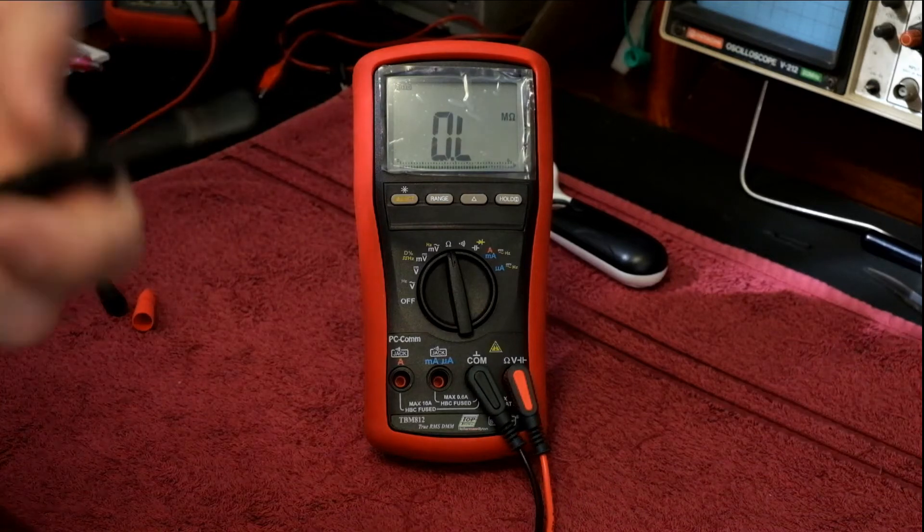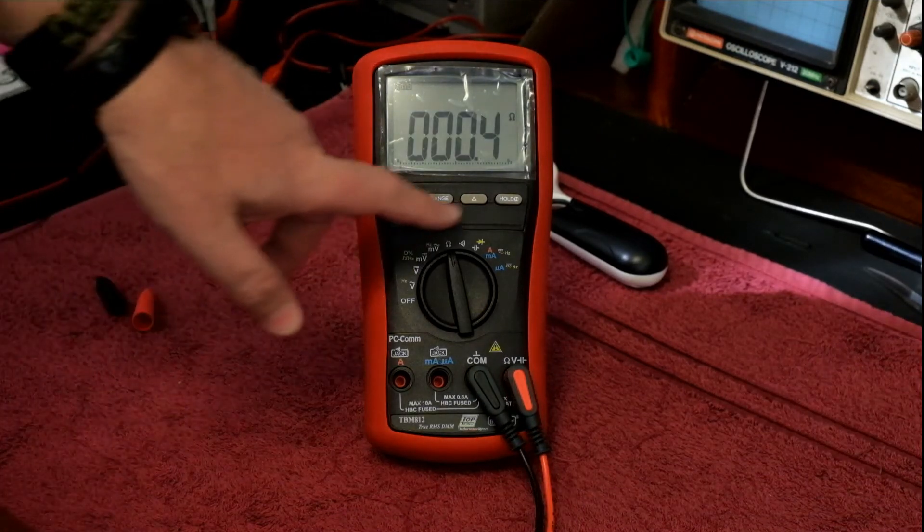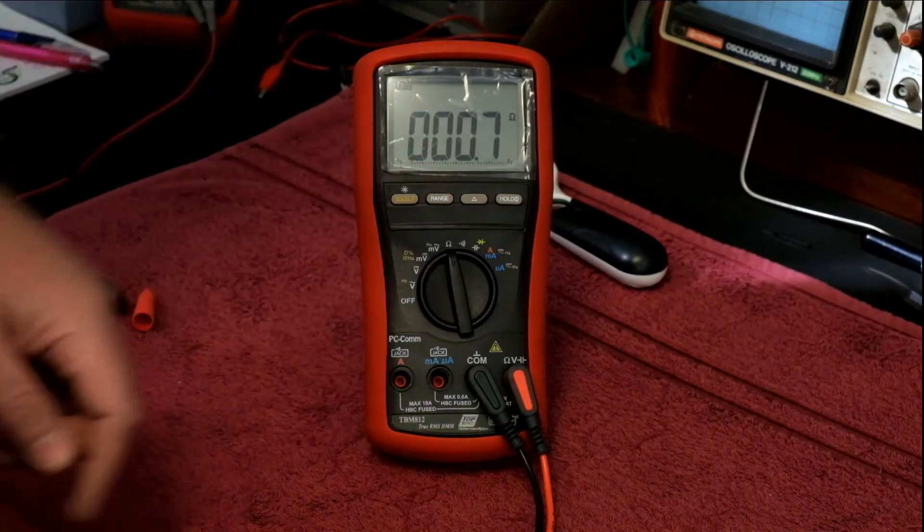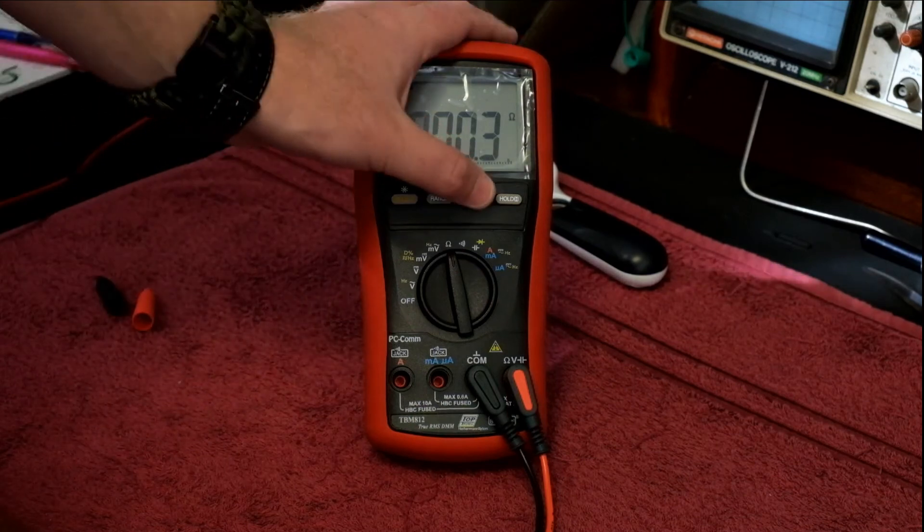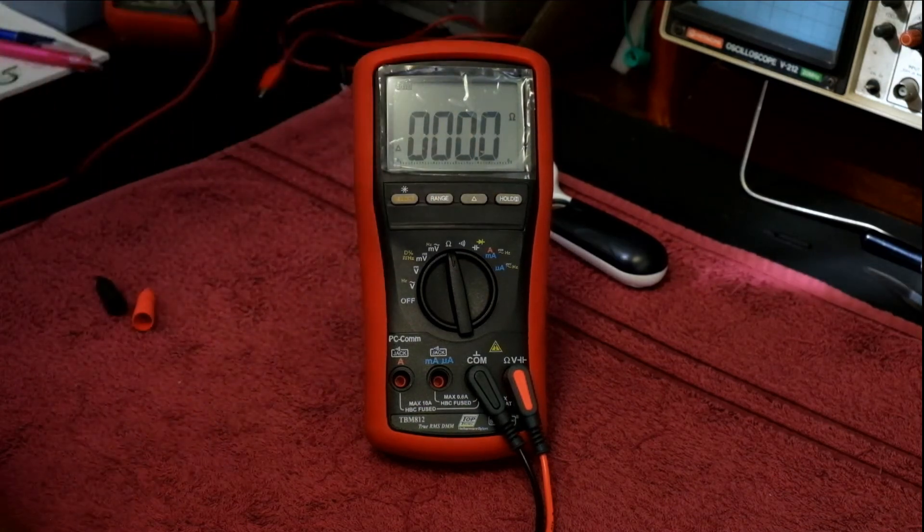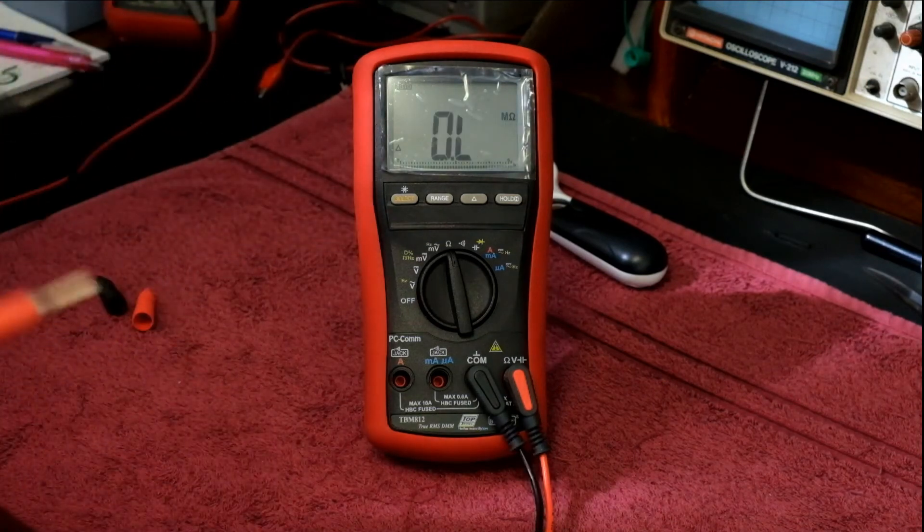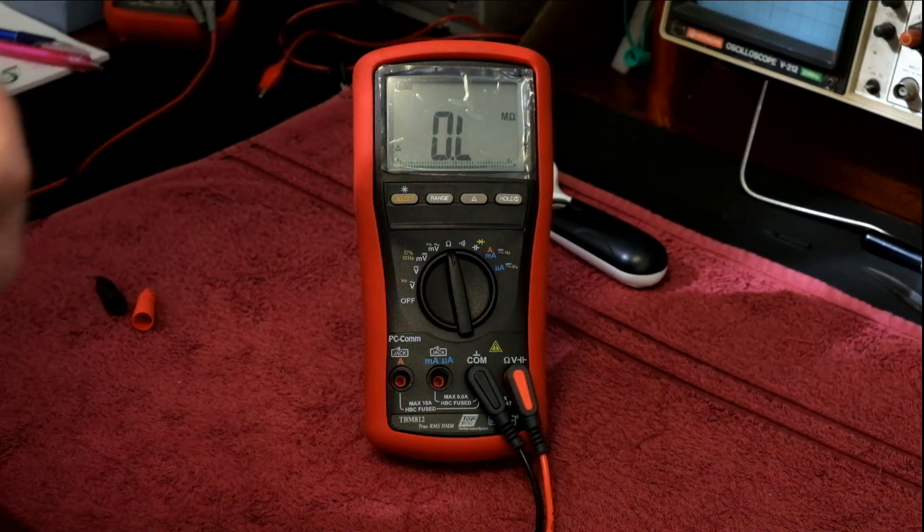So if the resistance of your leads is say 1 or 2 ohms, you can take a reading relative to that. Like if I short the two leads out, we do have some resistance there. If you want to get 100% accurate 0 resistance, you can take your measurement now and it will be more accurate.